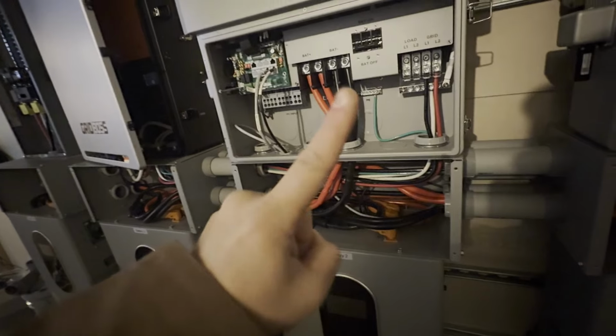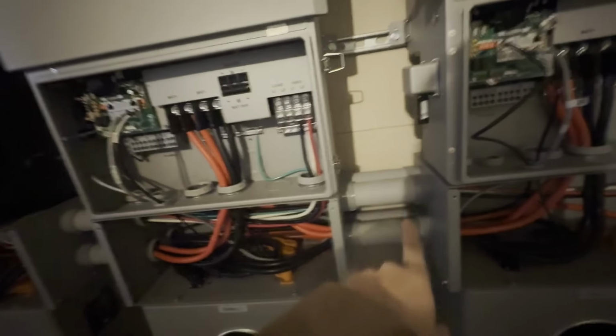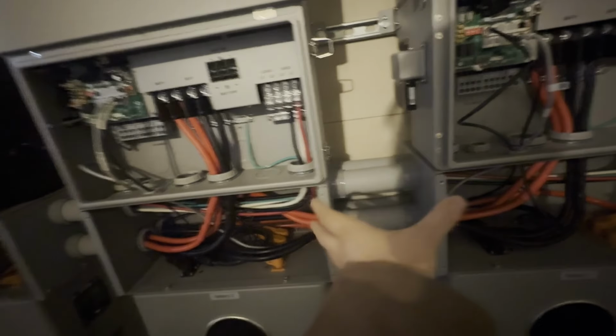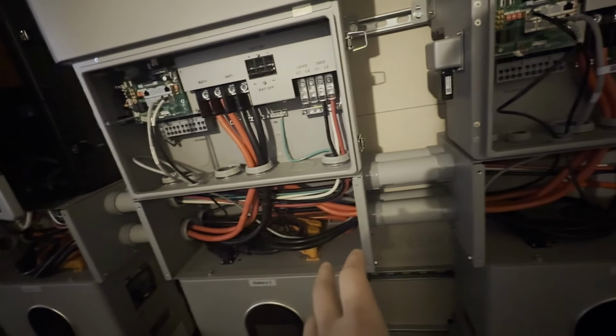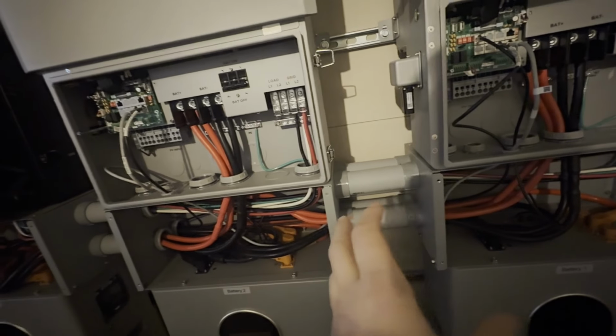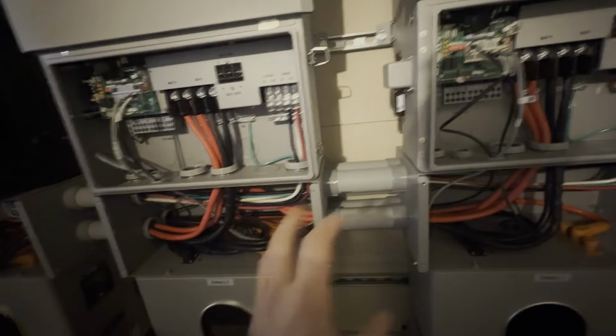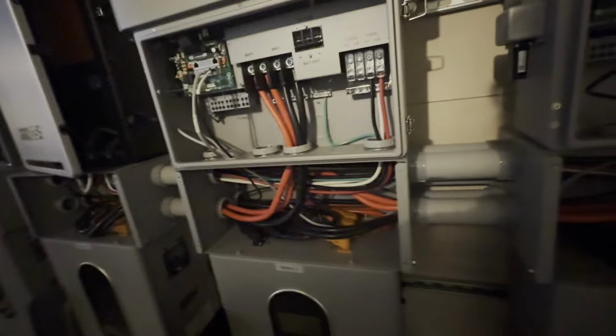Some of you may have an electrical background and may ask, if you've got multiples going through a conduit, don't you have to derate them? That's what I thought, so I did some more research. If the conduit run—or raceway, as they call it—is less than 24 inches long, then I don't have to do that derating based on the number of current carrying conductors, which is good, because otherwise I'd have had to upsize a lot of this stuff, and that would have been a pain.